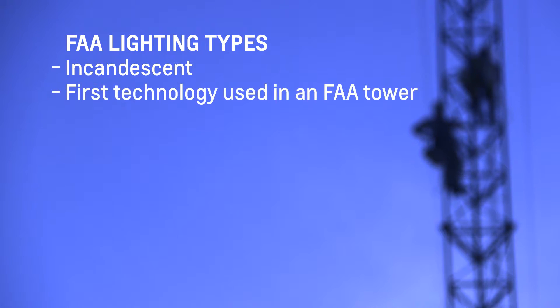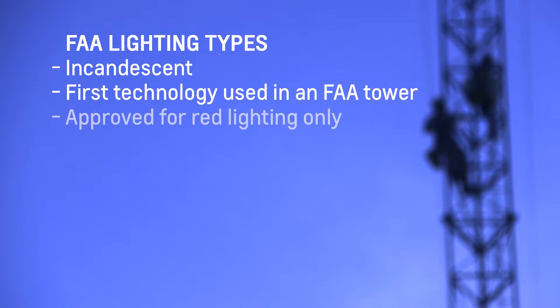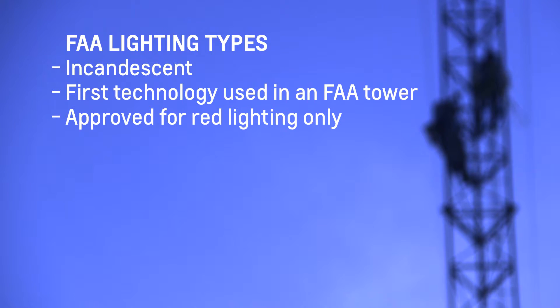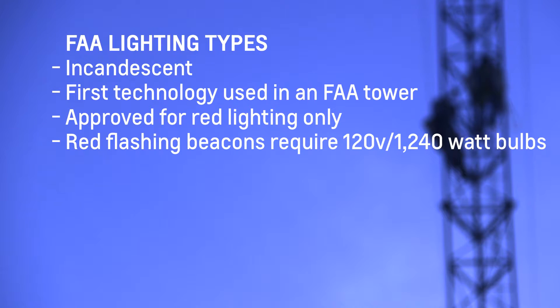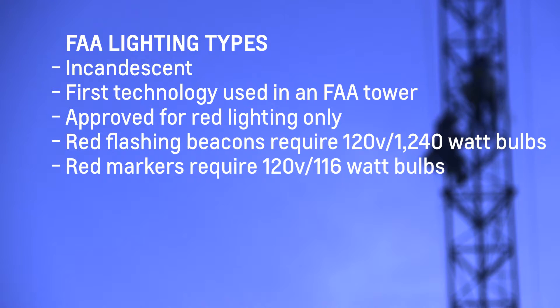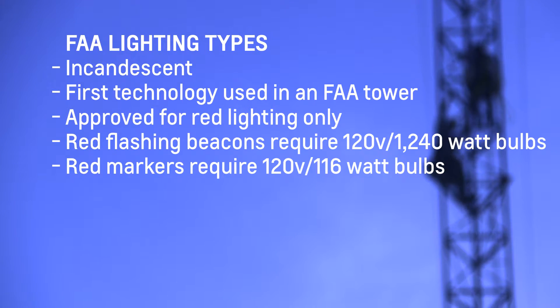Lighting technologies - Incandescent. Incandescent lighting was the first technology used in an FAA tower application, dating back to 1915. Incandescent systems are approved by the FAA for red lighting only. Incandescent bulbs are the cheapest and easiest to replace; however, they have the highest energy consumption and typically require relamping annually. To meet the FAA spec, red flashing beacons require 120 volt, 1240 watt bulbs, and red markers require 120 volt, 116 watt bulbs. Typically, these bulbs can only be sourced from specialty lighting distributors.